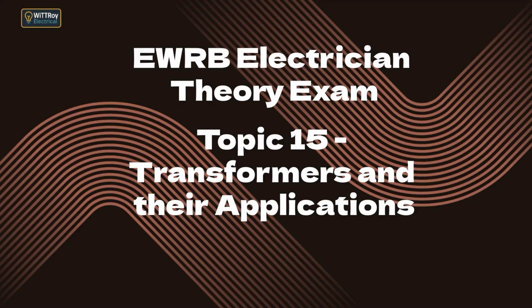15.1i Explain the term regulation as applied to transformers. Regulation is the percentage change in secondary voltage between no load and full load conditions. A transformer with good regulation maintains stable output voltage even as load varies. Poor regulation means voltage drops significantly under load. Lower regulation percentage is better.